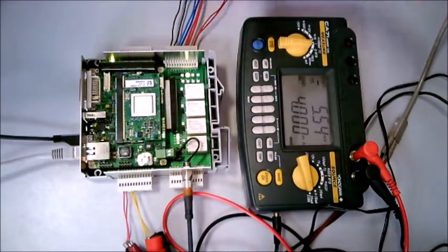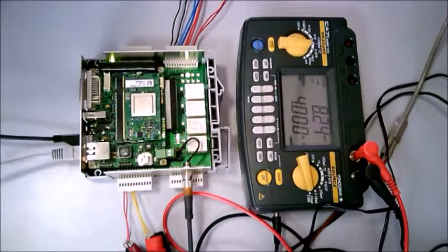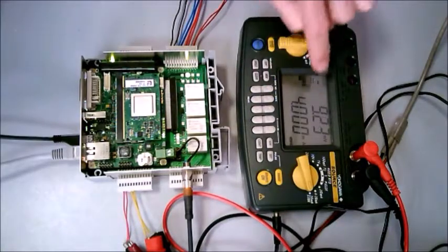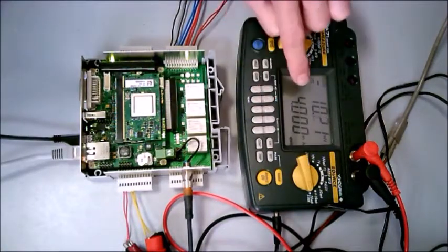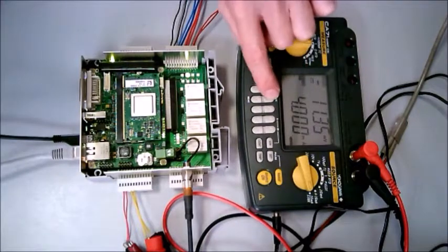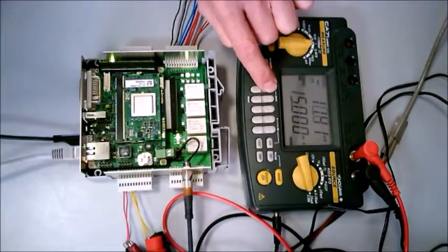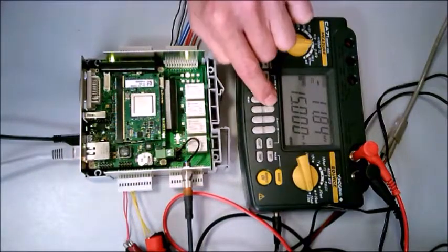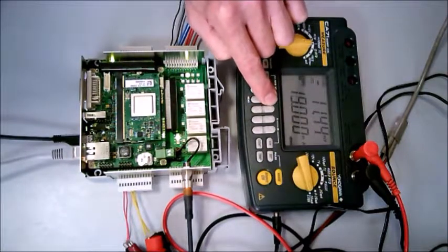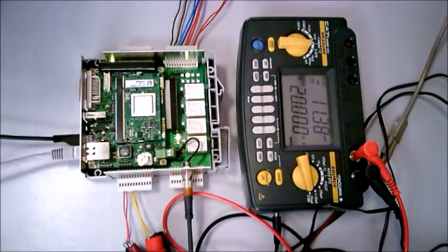It is important to have a very well calibrated multimeter from a range coming from 4 up to 20 milliamps, okay? Which will be our full scale range.